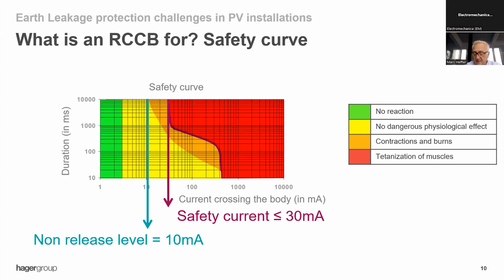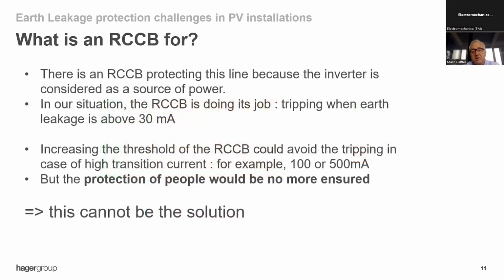So that's for the RCCB and why we put an RCCB. Here we put an RCCB because the inverter is considered as a source of power, of course, inside of your building. And therefore we have to protect the line that is downstream of this source of power. And in our situation, the RCCB is doing its job. It means it has to trip when the earth leakage is above 30 milliamps. That's absolutely normal.